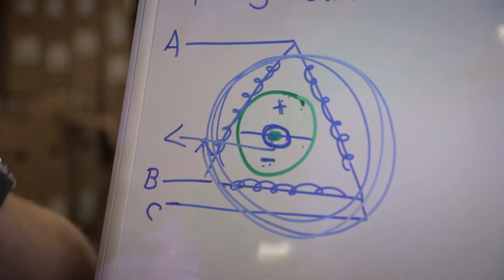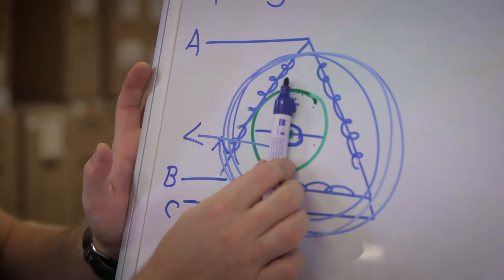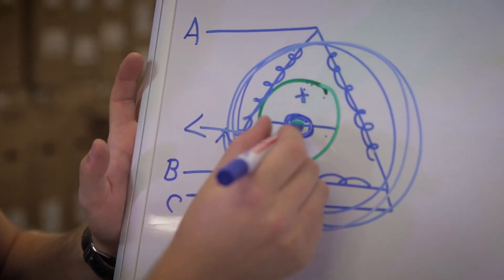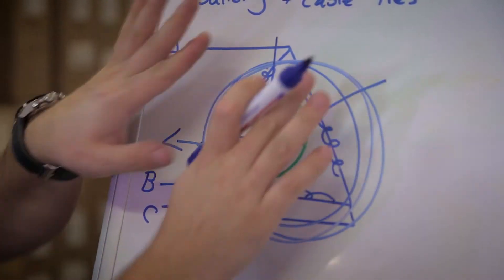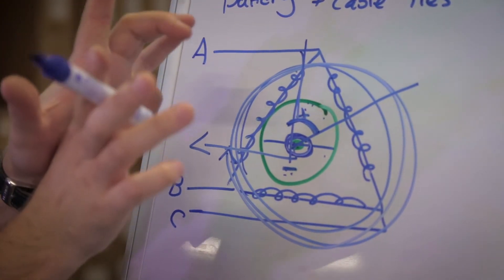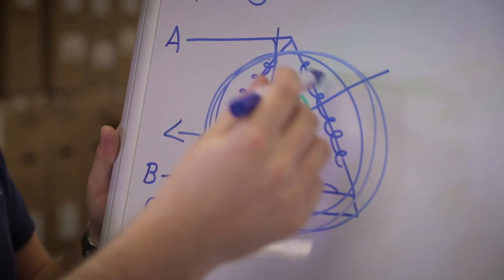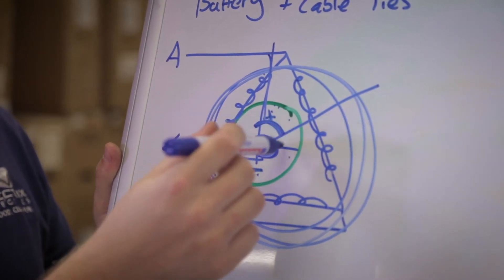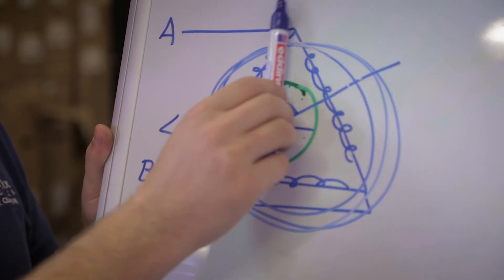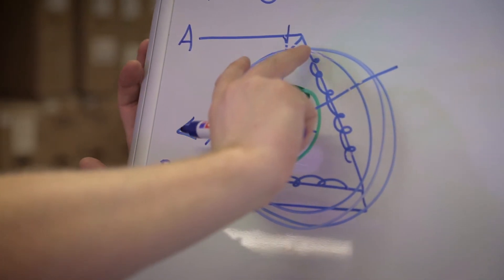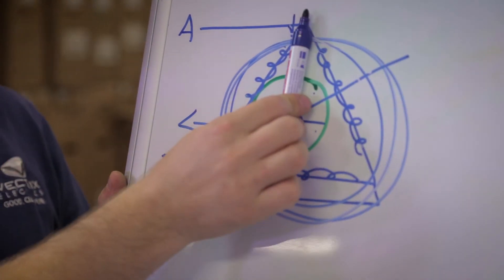If this sensor sends its zero here but the magnetic field has its zero here, this angle is actually an offset that we will have to compensate electrically. So this procedure forces the motor to rotate and sends the feedback of the encoder. It determines what is the angle and applies this offset into the code. So when the motor drives the magnetic field, it will apply with a certain degree of advance or retard in reference to the position of the rotor.